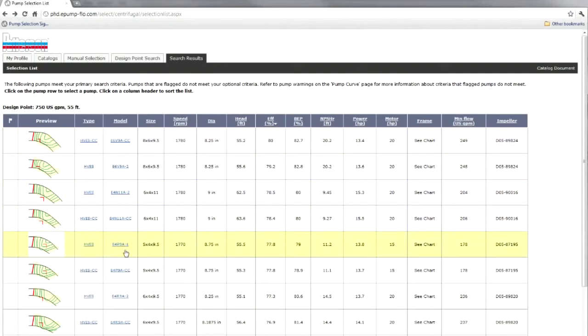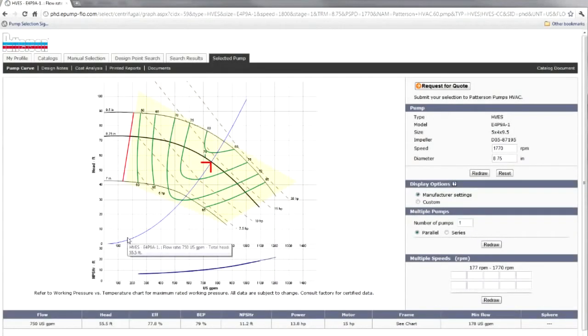And my brake horsepower is about the same. Of course it's going to be the same. It's going to be very close because the efficiencies are close, and it's still moving the same amount of water at the same amount of pressure. And based on the formulas that you can find on our website and in other classes we teach, that's what generates that water horsepower, the amount of energy to move water at a distance.